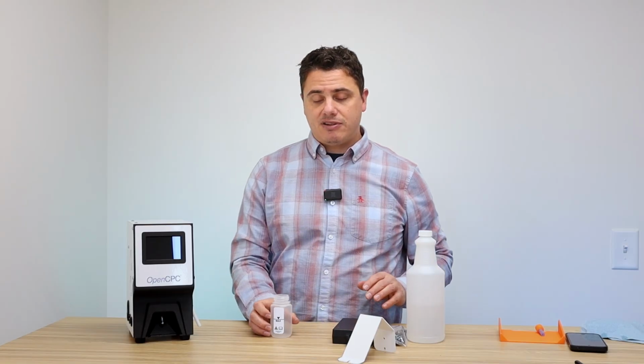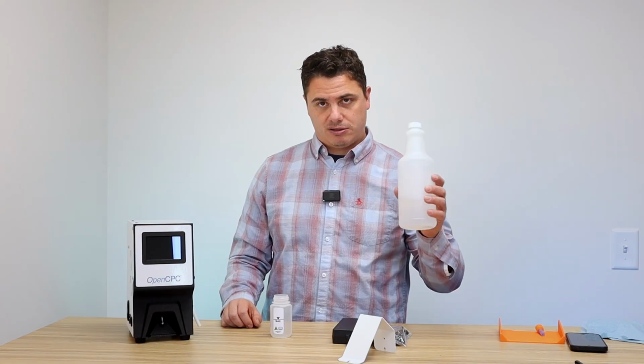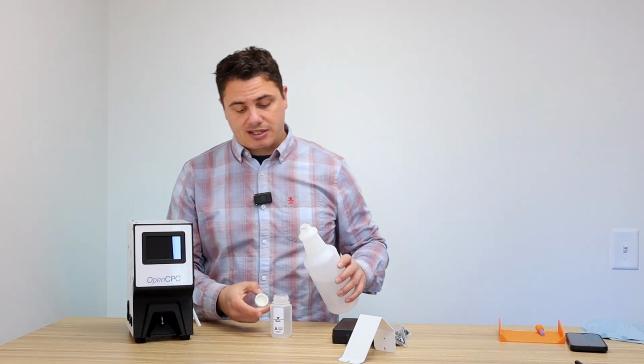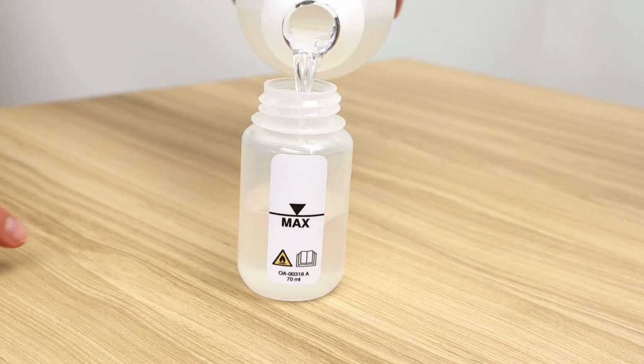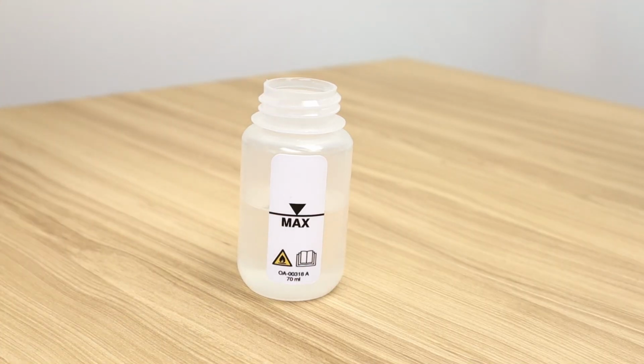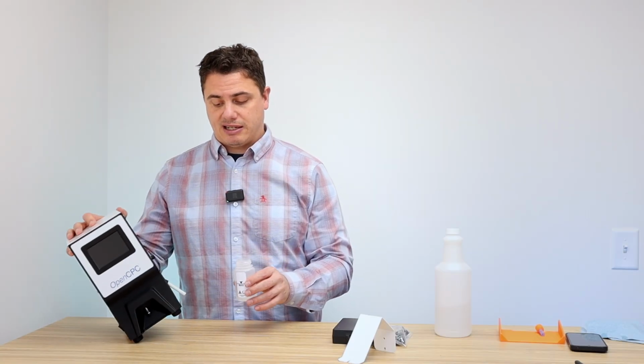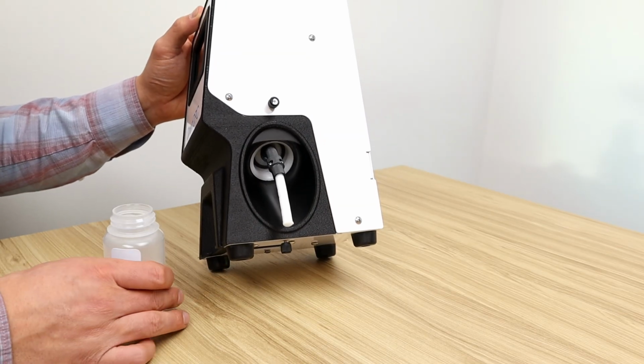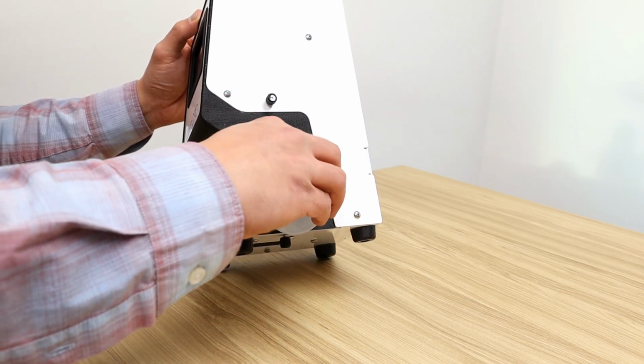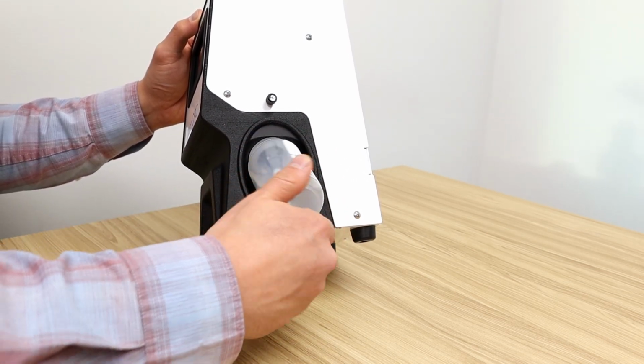We'll need to add 70 milliliters of 2-propanol to the bottle. There is an indicated max fill line, and you'll just need to fill until you get there. With the bottle full, simply tip the CPC on its side, guide the opening of the bottle through the wick, and tighten to hand tight.